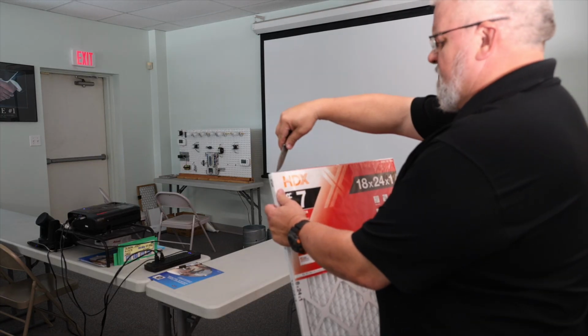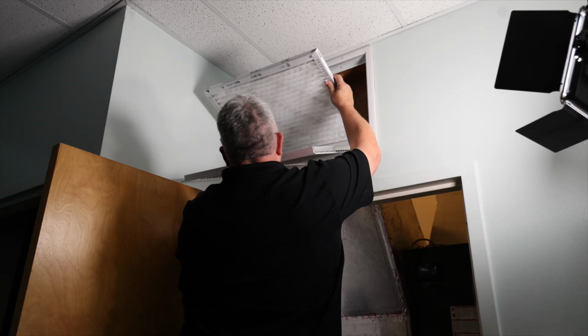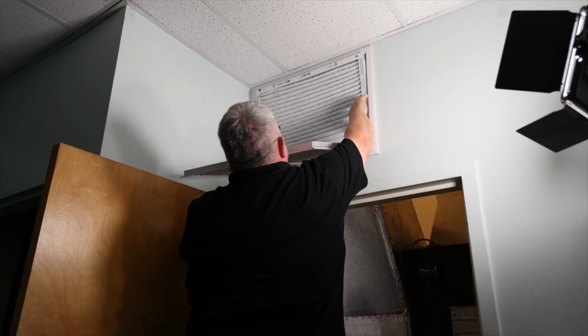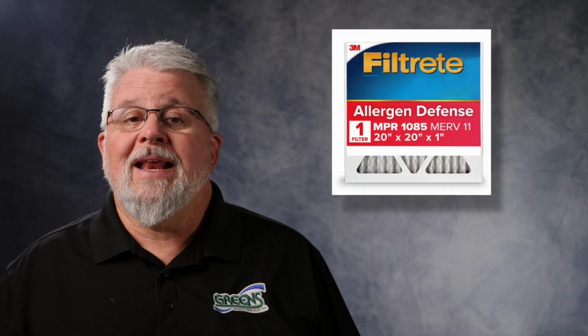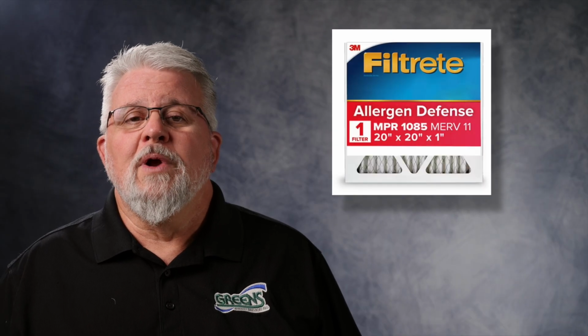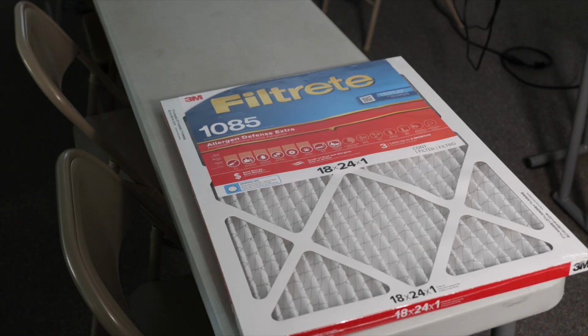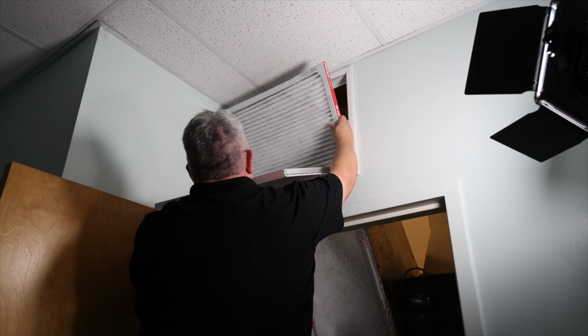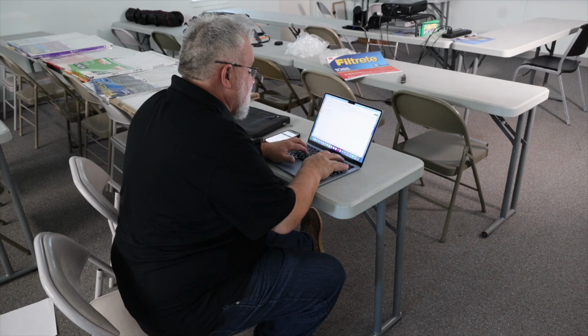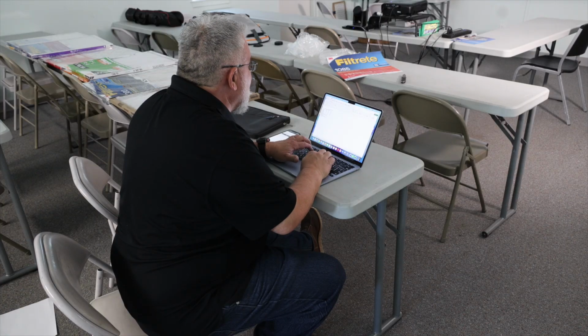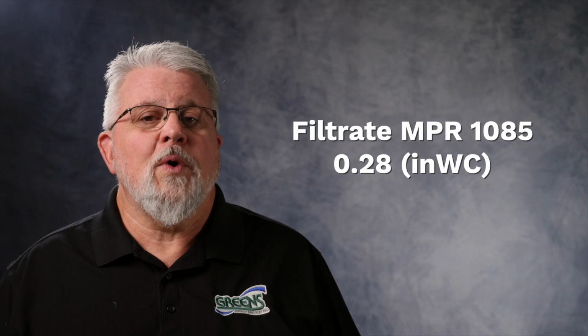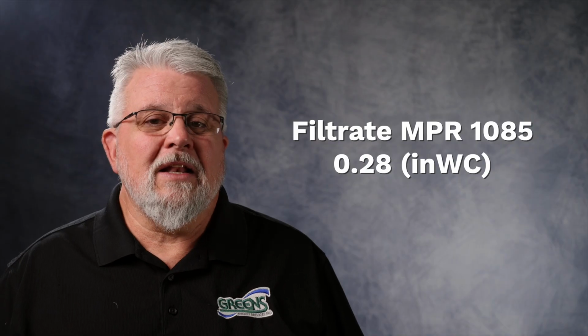This filter had a thicker media and was electrostatically charged, but again, I still found it fairly flexible structurally. The pressure drop measured 0.29 inches, and then we tested the Filtrete 1085. This is where Filtrete really started separating itself from the pack. This MERV 11 filter uses a tighter pleat spacing and a better construction than the filters we've already tested. And despite being a higher rated filter, the pressure drop came in at 0.28 inches. That's slightly lower than the HDX filter we just tested.